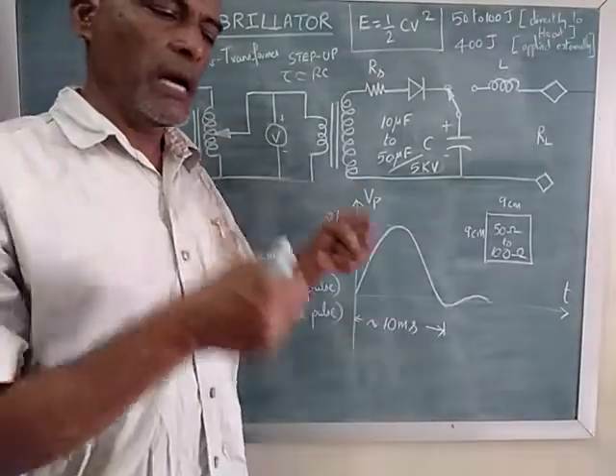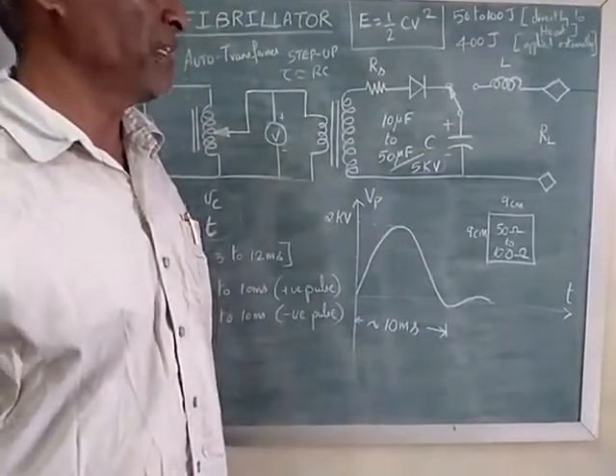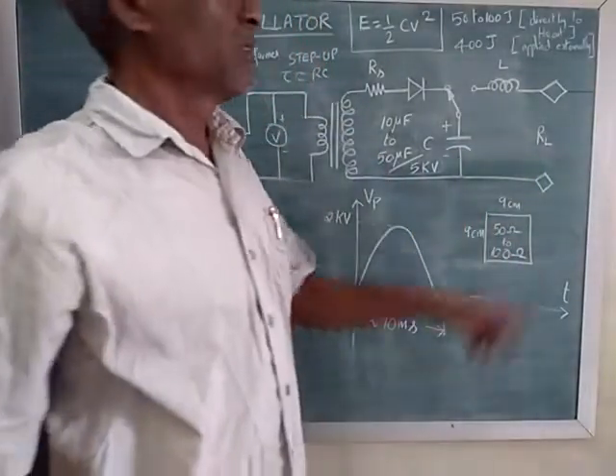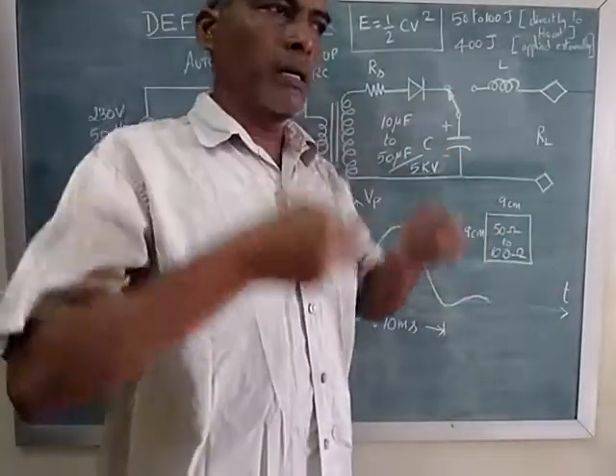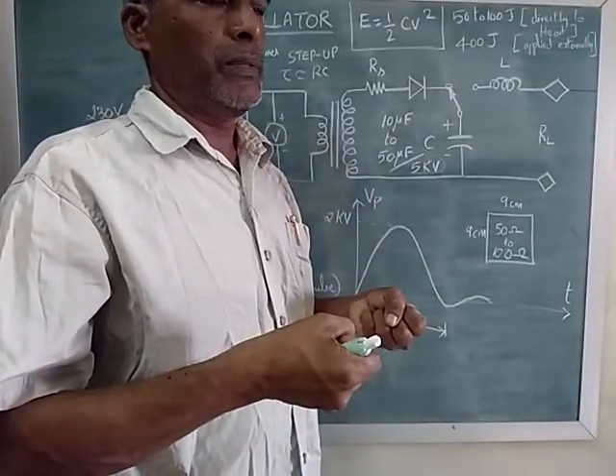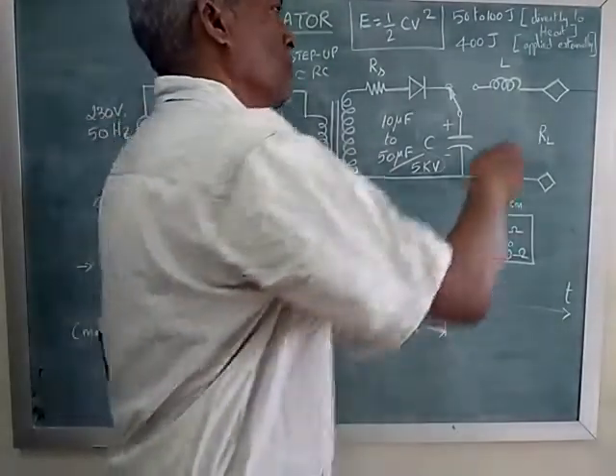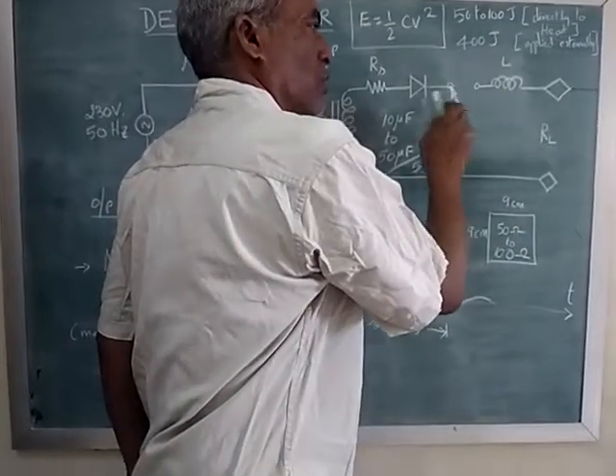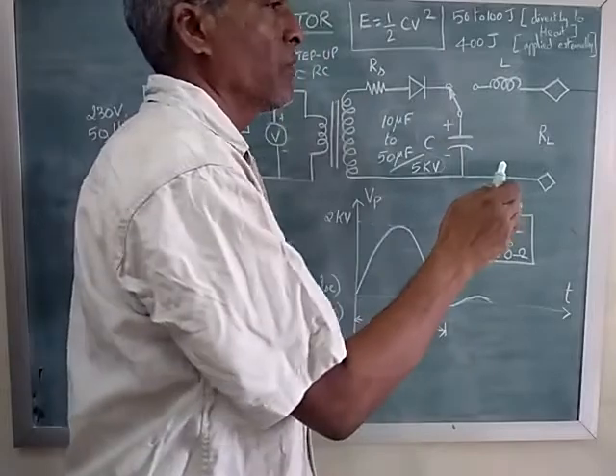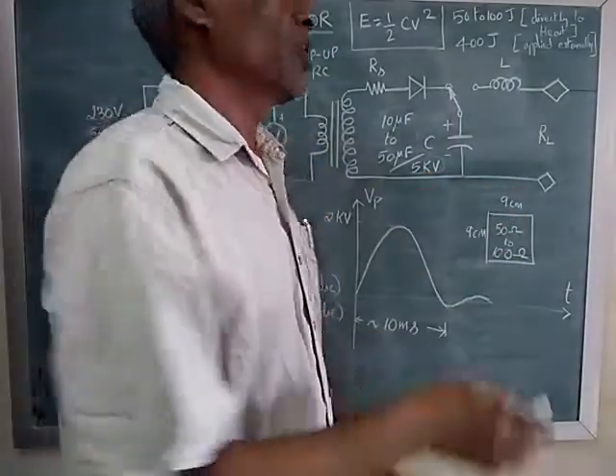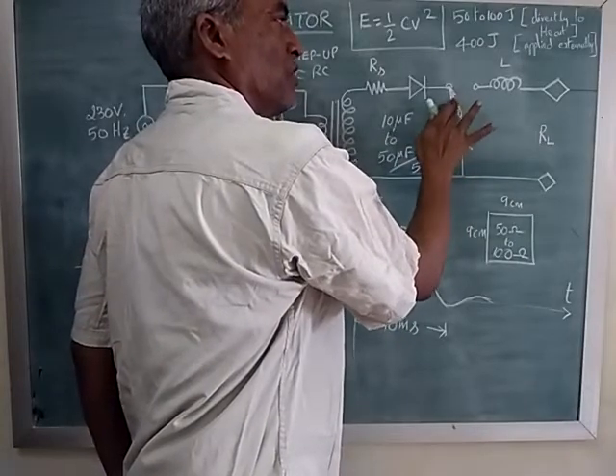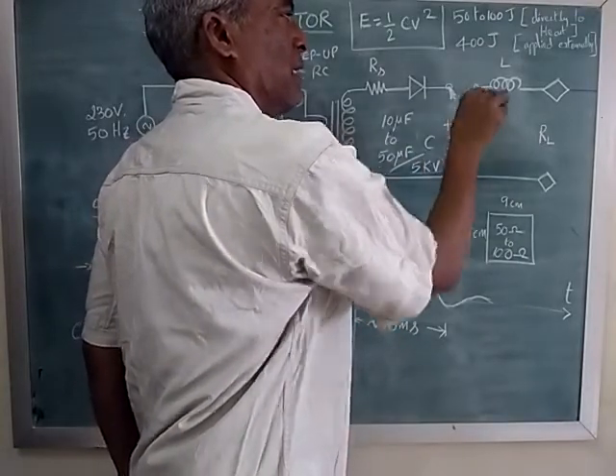So what happens is the capacitor charges. So when you want to apply to the patient, these two are electrodes. So these two electrodes are pressed on the chest of the patient. So the switch is initially connected here for normal charging. But when you apply for the shock for the patient, then you have to connect the switch here. That means this portion is disconnected and it gets connected here.